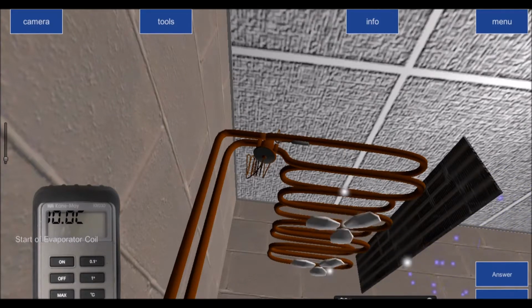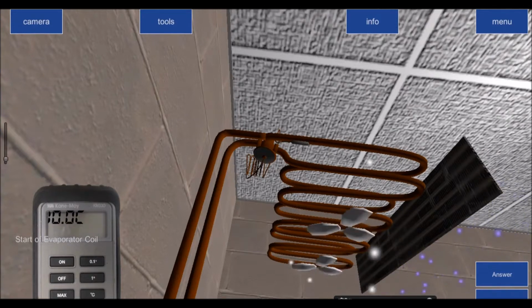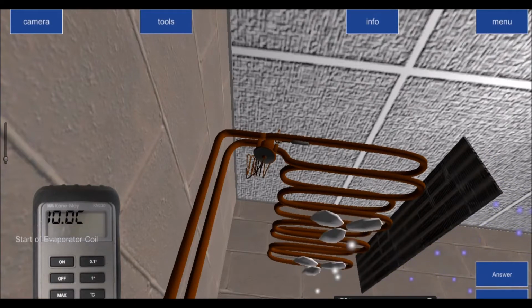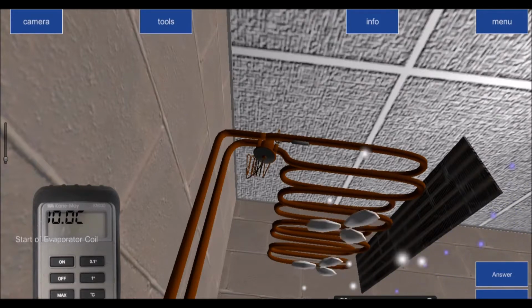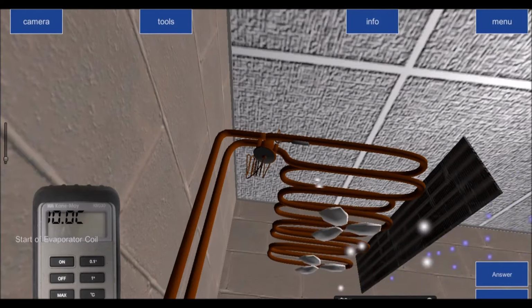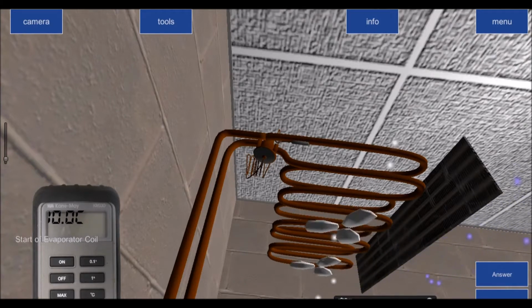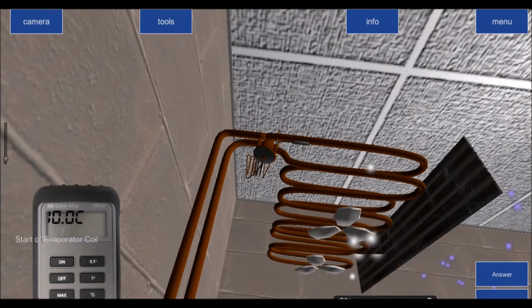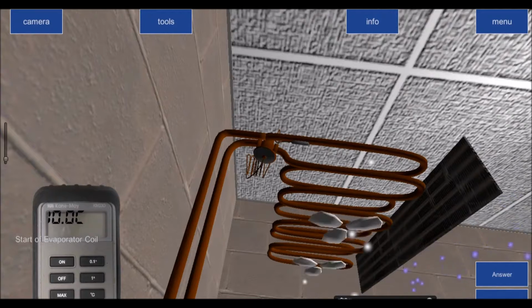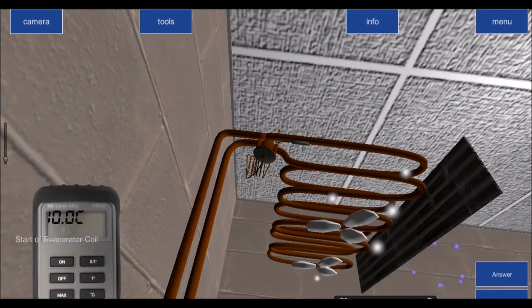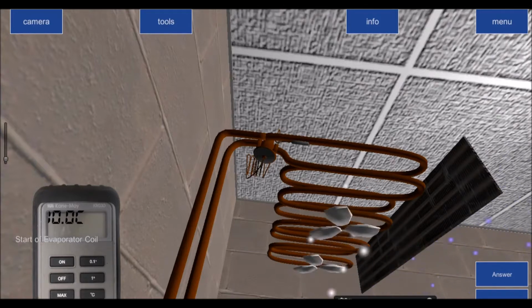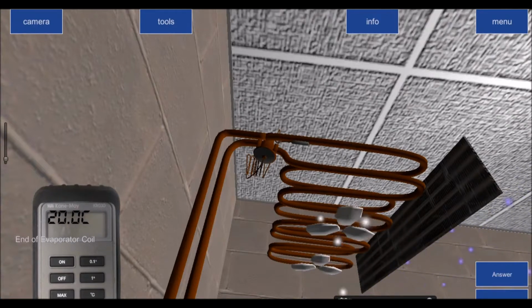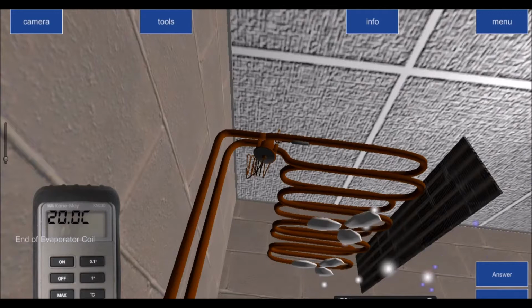When we have a liquid and vapor mix, our latent heat will be a saturated latent heat. In other words, it's going to be constant pressure and temperature going through the evaporator. So when I measure with the thermometer, I will get my constant pressure temperature, or my constant 10 degrees temperature. As soon as 100% vapor occurs inside the evaporator, all the thermometer ever does is measure sensible heat. The thermometer is able to pick up on the sensible heat change. So that's how we can get our superheated vapor temperature. Or I'd rather just say that we get our vapor temperature at the outlet and we get our liquid vapor mix temperature at the inlet.